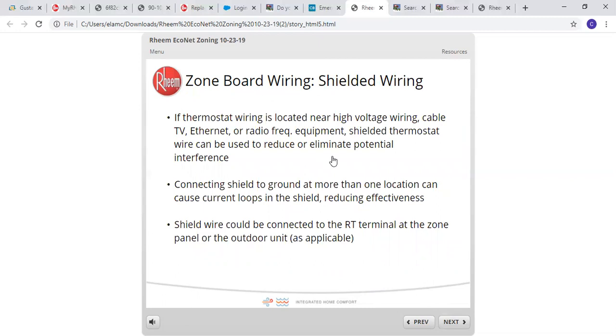Shielded wiring. If your thermostat wiring is located near high voltage wiring, cable TV, Ethernet, or radio frequency equipment, shielded thermostat wiring can be used to reduce or eliminate potential interference. Connecting shield to ground at more than one location can cause current loops in the shield, reducing its effectiveness. Shield wire can be connected to the RT terminal at the zone panel or outdoor unit as applicable.